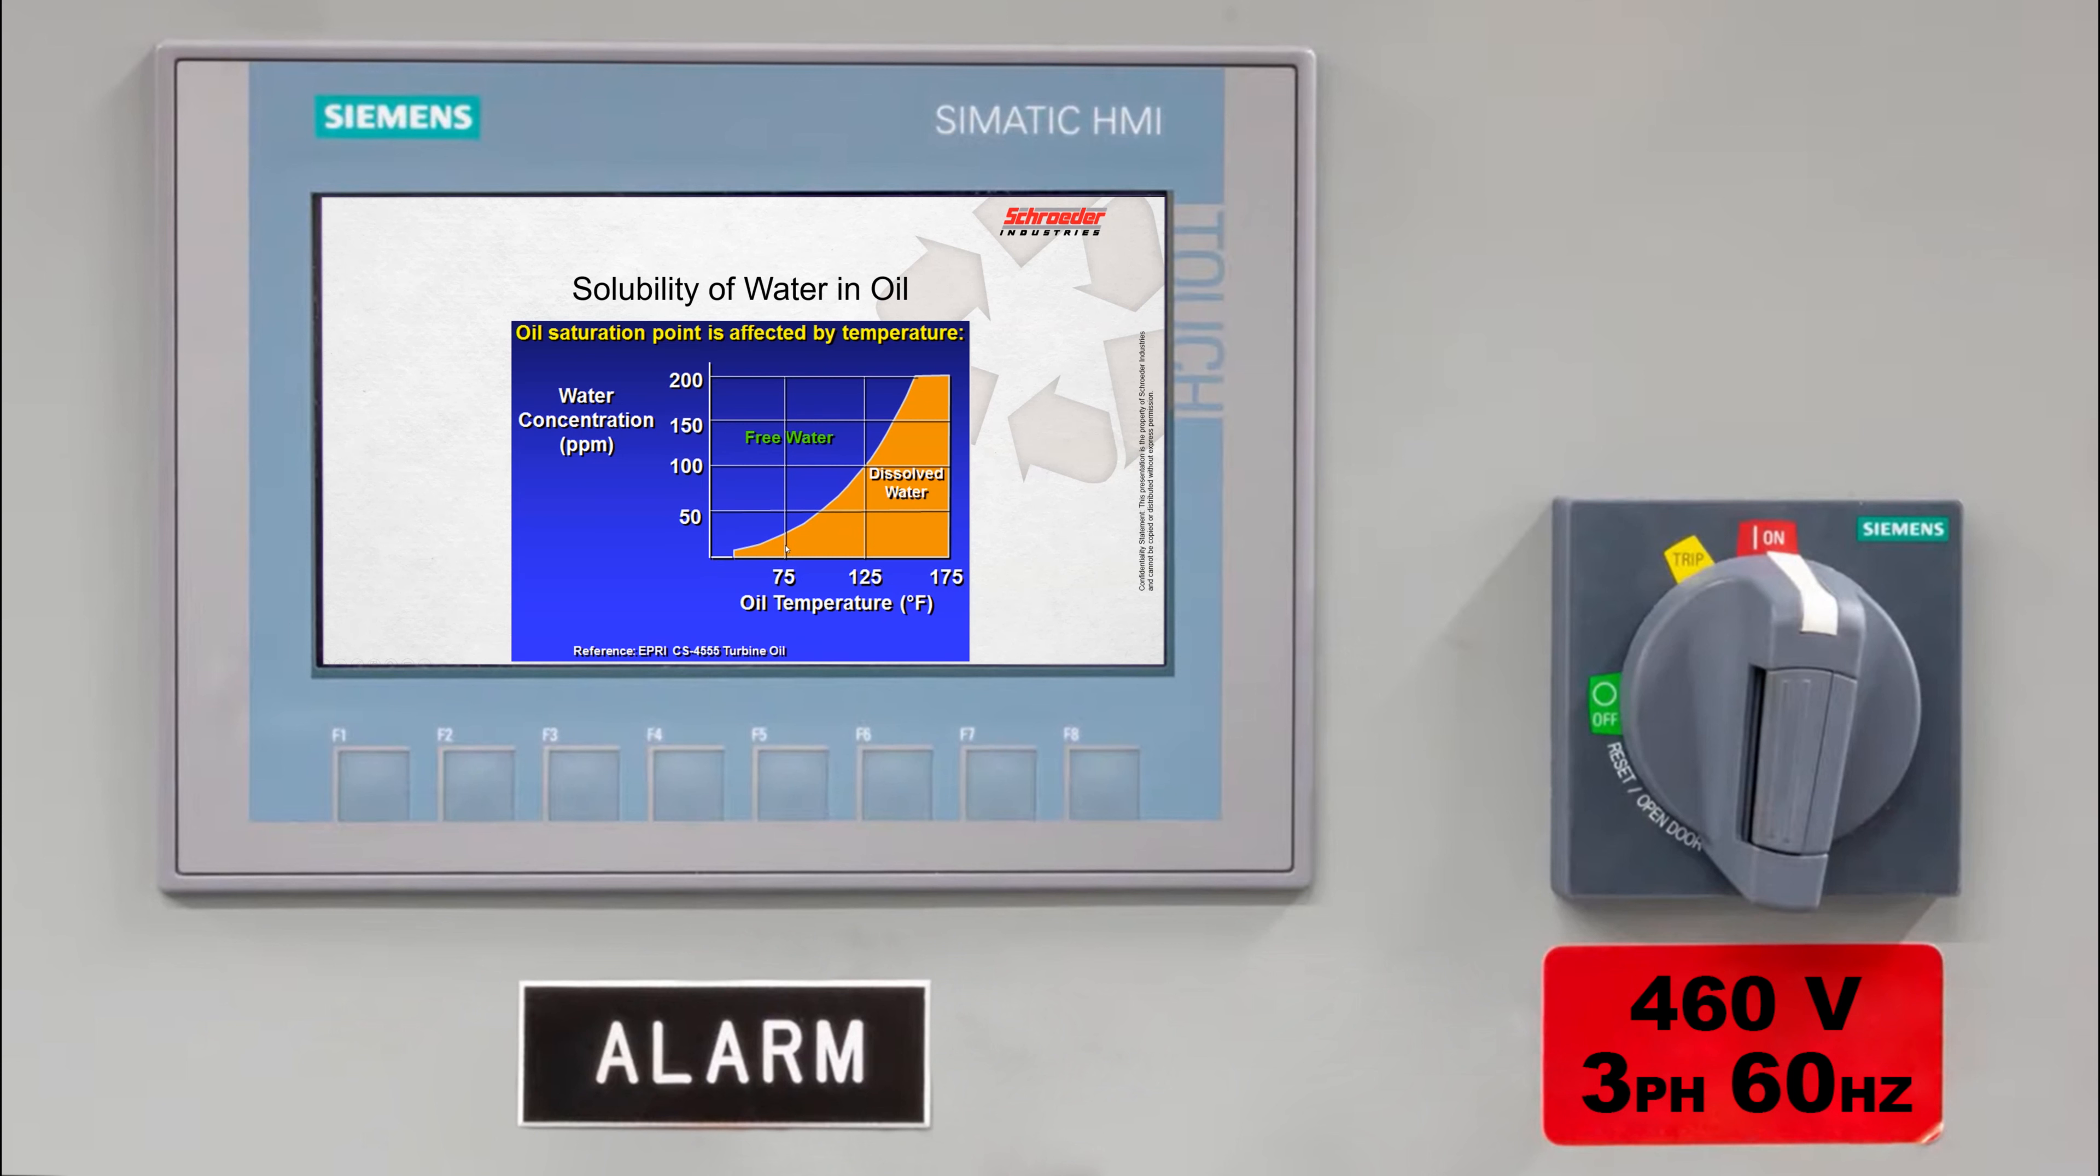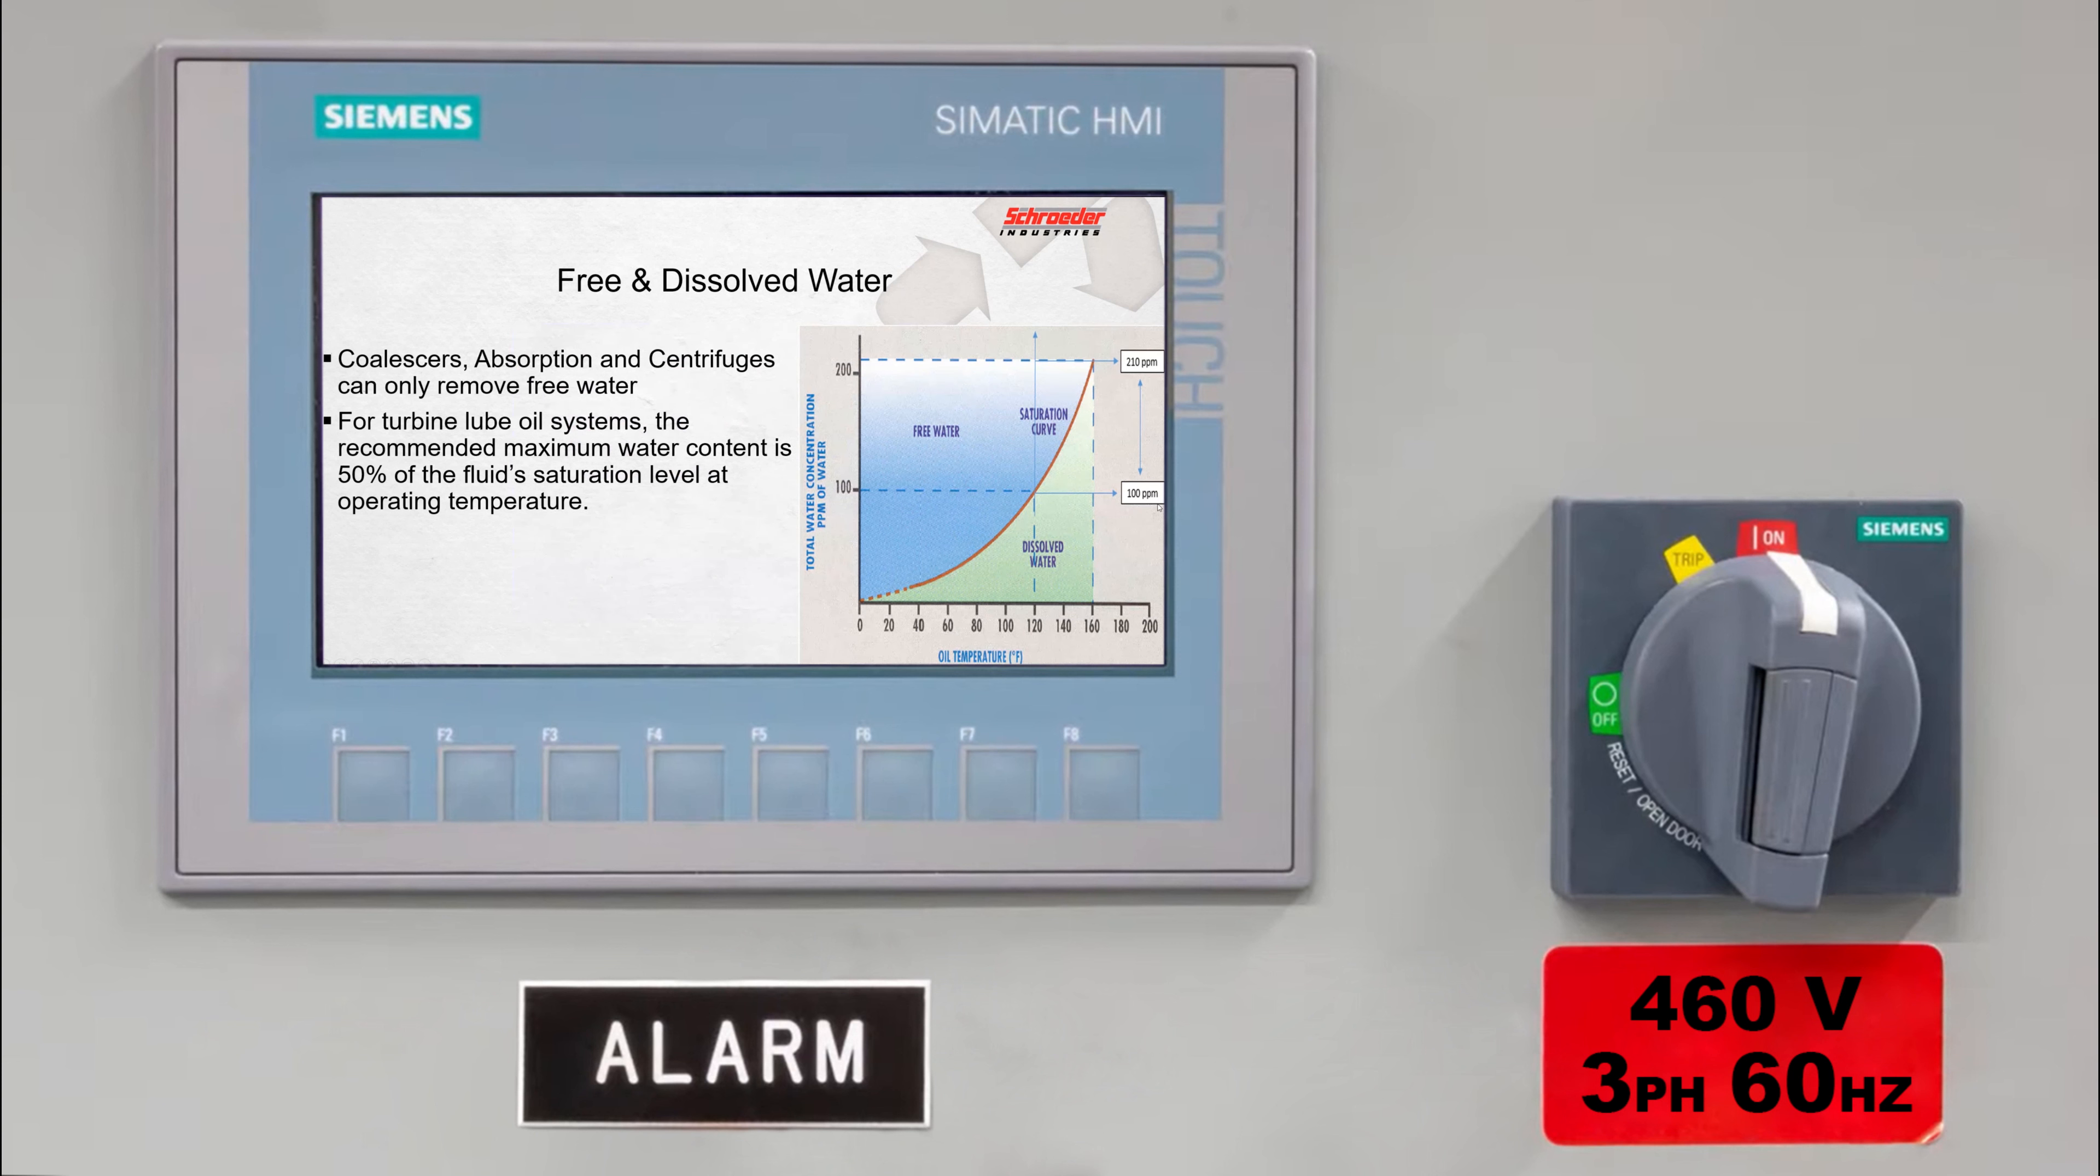In this customer's application with this type of fluid, looking at this curve, my recommendation to them is going to be we want to keep this fluid somewhere around below 50 PPM, roughly around 25 if not slightly below, so there's no free water present when the system's at rest.